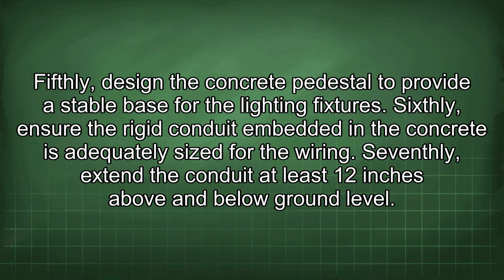Fifthly, design the concrete pedestal to provide a stable base for the lighting fixtures. Sixthly, ensure the rigid conduit embedded in the concrete is adequately sized for the wiring. Seventhly, extend the conduit at least 12 inches above and below ground level.